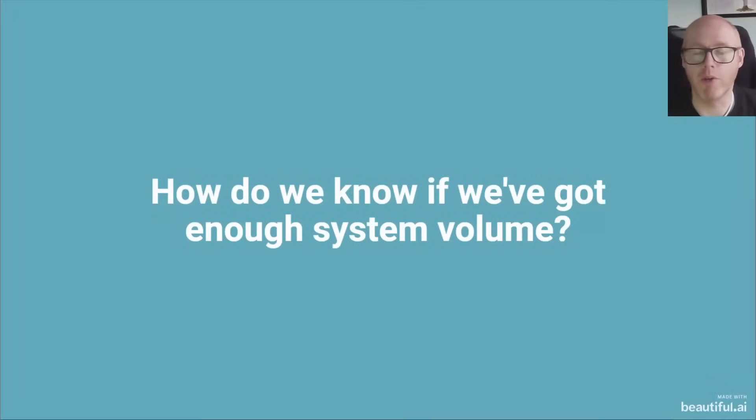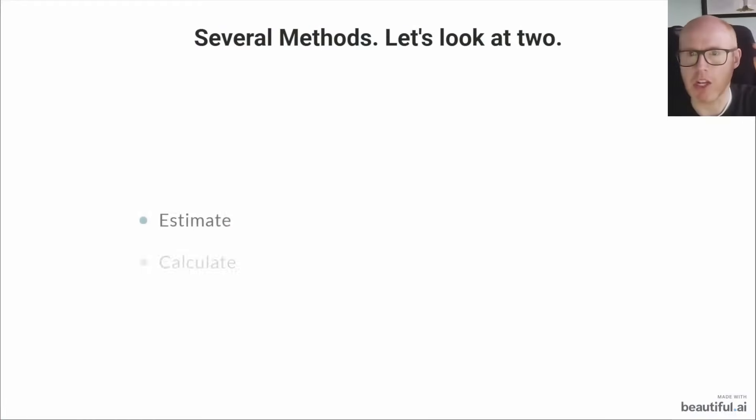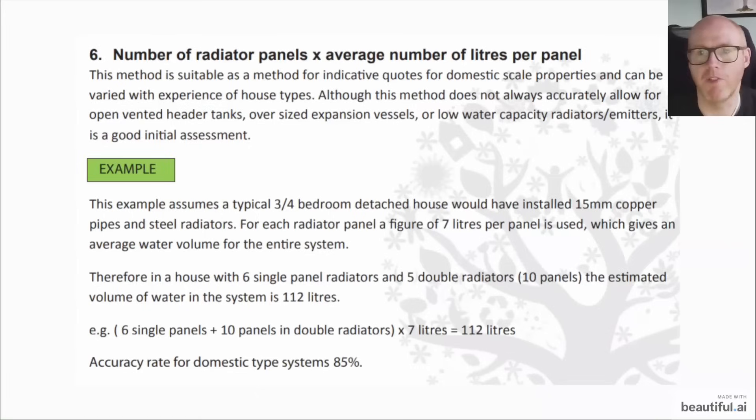How do we know if we've got enough system volume? There's a couple of methods but today I'm just going to look at two. There's one that's like a rule of thumb to estimate it, and then a very quick and easy way to calculate it. The best method is to drain your whole system, check your water meter, and then fill the system through the filling loop and check your water meter again. Then you can know exactly how big your system is very accurately.